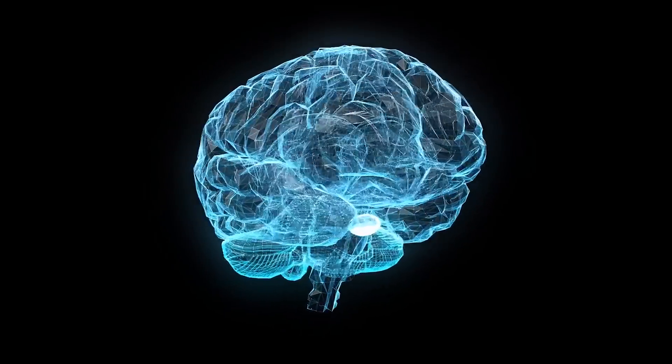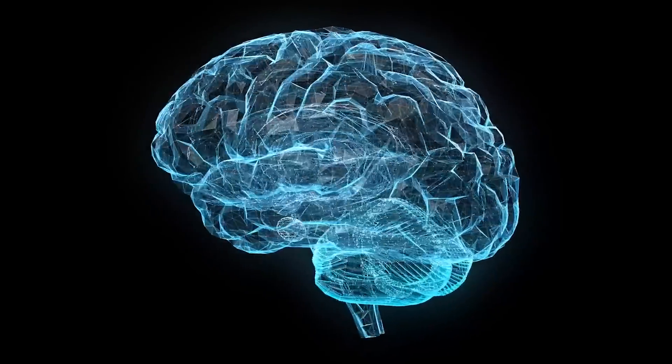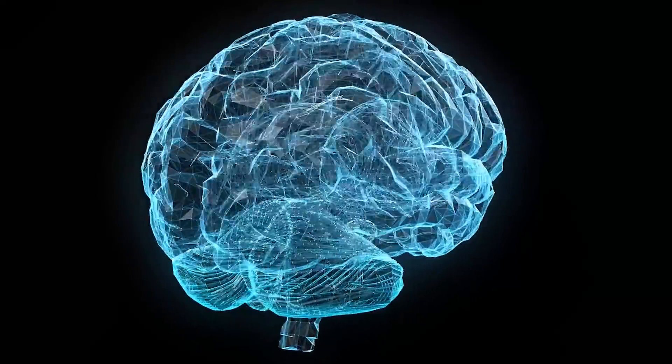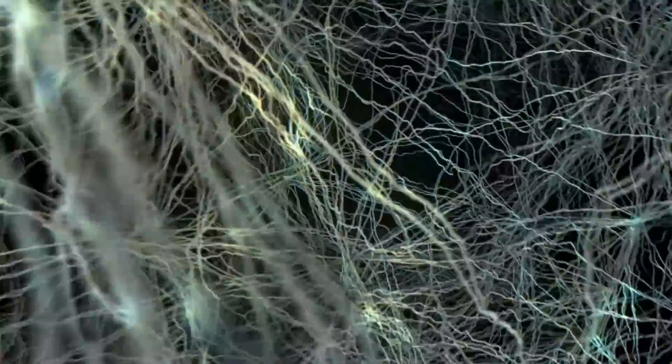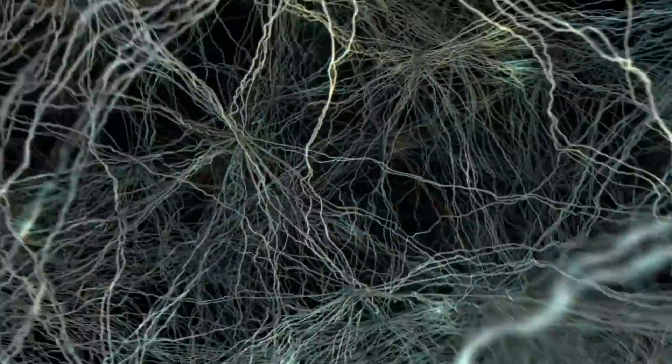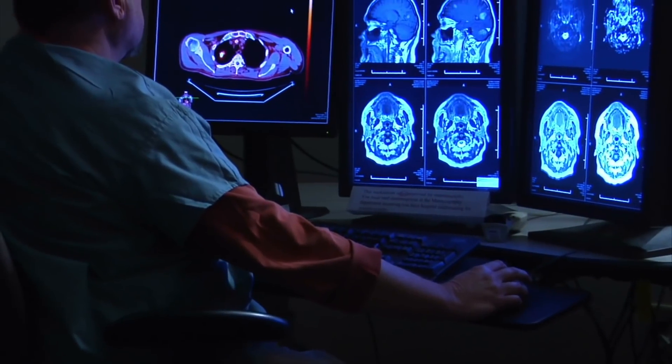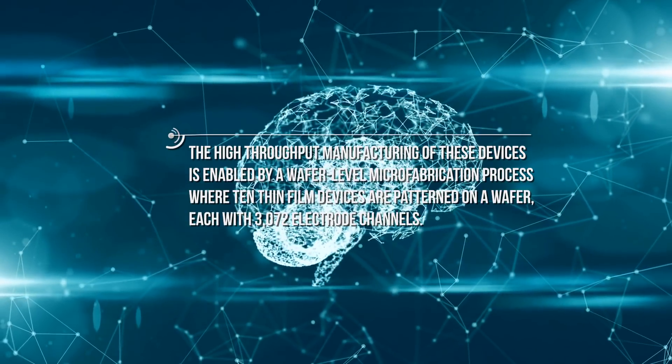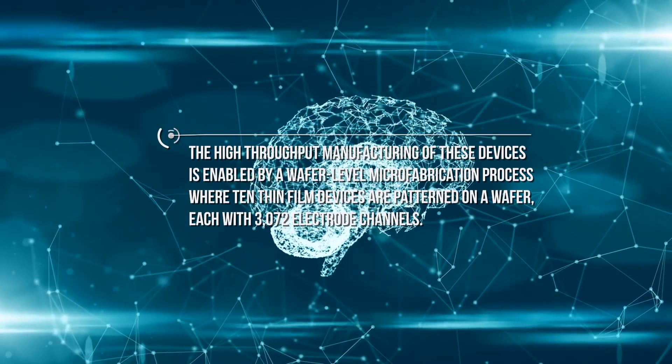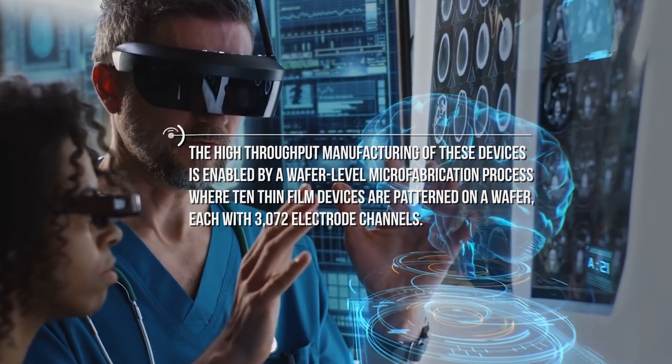Polyimide is the main dielectric and substrate used in these microelectrode probes where they encapsulate a gold thin-film trace. Each thin-film array is composed of a thread area featuring electrode contacts and traces along with a sensor area where the thin-film interfaces with custom chips to enable signal amplification. The high-throughput manufacturing of these devices is enabled by a wafer-level microfabrication process where 10 thin-film devices are patterned on a wafer, each with 3072 electrode channels.